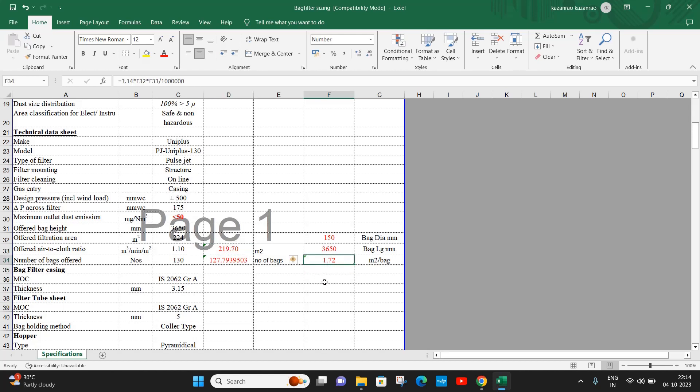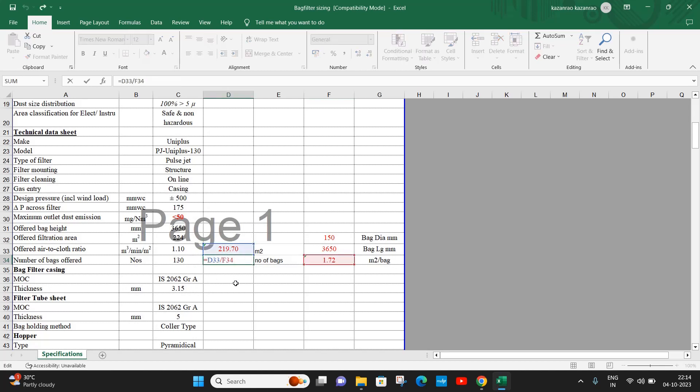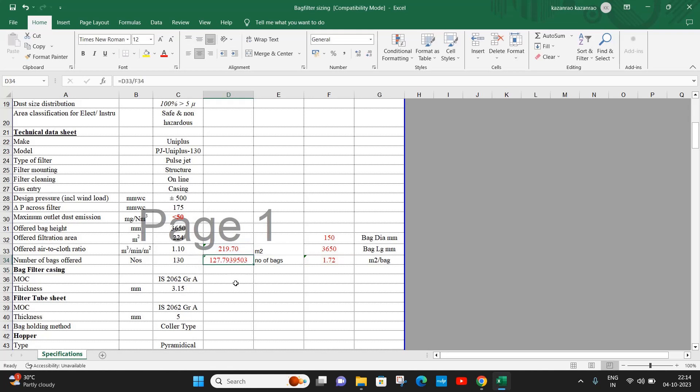So the actual number of bags required for the bag filter is total area required divided by area of a single bag. So it is 219.7 divided by 1.72, which is 128 bags. Accordingly, bag filter of 130 bags are selected. This is how bag filter is sized.